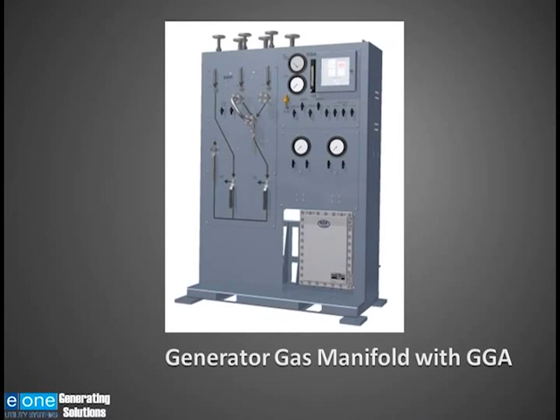This is a picture of the cabinet that houses the components shown in the previous P&ID. Again, the two lower gauges are the CO2 supply pressure and H2 supply pressure. Behind those are the transmitters that monitor those two and send a signal to the control room. The two upper gauges, one is a fan differential pressure gauge, and the other one is a case pressure. The little door on the upper right hand is the door to the analyzer. The purity analyzer is behind that door.